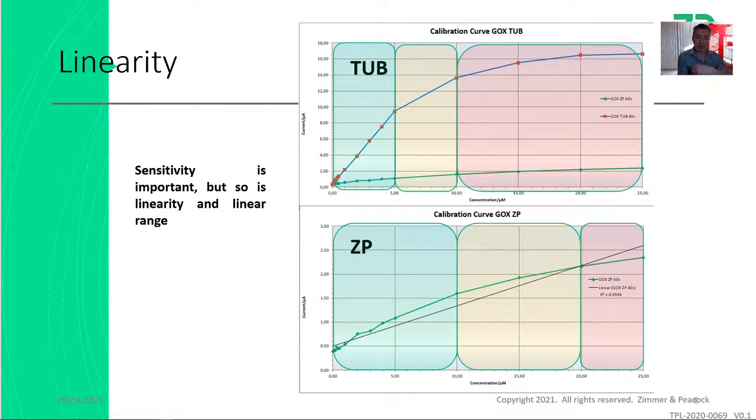And I would also say this, that you're trying to make a biosensor. A sensor by its nature should not have so much activity that it completely converts the sample into product. If you're working in a very small volume and you have a very active enzyme sensor, you can end up converting all of the glucose, for example, into gluconic acid. That's really a synthesis. When you're trying to sense, when you're trying to do an analysis, you don't actually want your sensors to necessarily be so active that they end up converting all the sample. Because as I say, that's synthesis, not analysis.